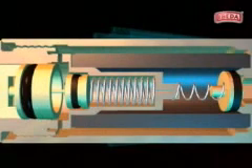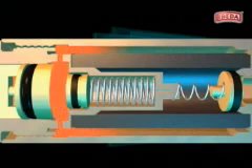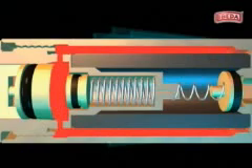A dust filter protects the non-return valve from contamination for long service life. When a flashback occurs, the hazard is very real and the flame must be extinguished immediately. A sintered nickel-chromium steel flame barrier extinguishes the flashback flame from the gas outlet side, preventing it reaching the gas on the inlet side and so prevents it from igniting. The gas non-return valve is also protected by the flame barrier, so that after flashbacks, no slow or sudden gas surge of air or oxygen into the distribution system or cylinder is possible.